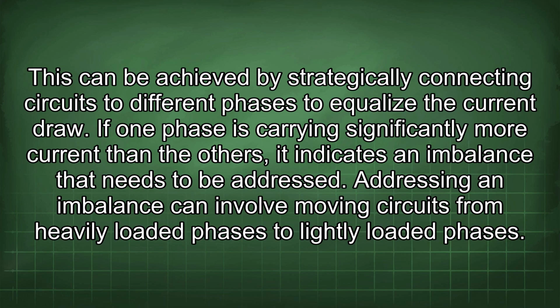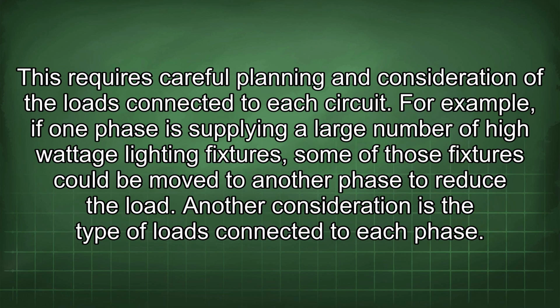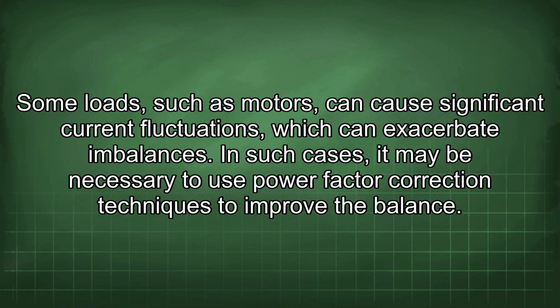Addressing an imbalance can involve moving circuits from heavily loaded phases to lightly loaded phases. This requires careful planning and consideration of the loads connected to each circuit. For example, if one phase is supplying a large number of high wattage lighting fixtures, some of those fixtures could be moved to another phase to reduce the load. Another consideration is the type of loads connected to each phase. Some loads, such as motors, can cause significant current fluctuations which can exacerbate imbalances. In such cases, it may be necessary to use power factor correction techniques to improve the balance.